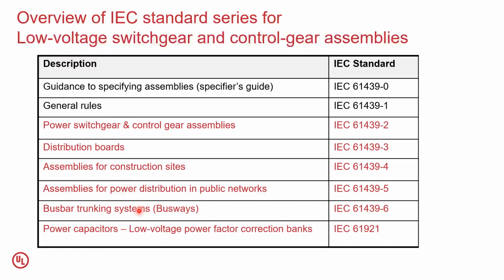So if you have a busway, then from this context, you will need two standards to be referred. One is 61439-6, that is the product standard, also called a specific part standard. And then you will also need the general rule standard, because that is where all your general requirements are actually specified. So these couple of standards I showed you, all of them will refer, depending on the context, back to the general rule standard. So that is just an example I wanted to share.